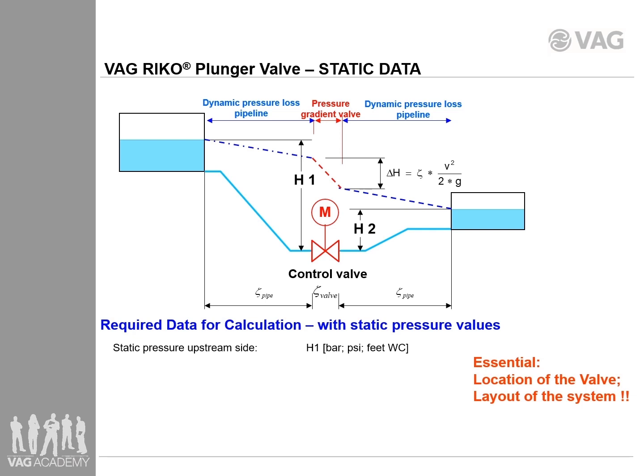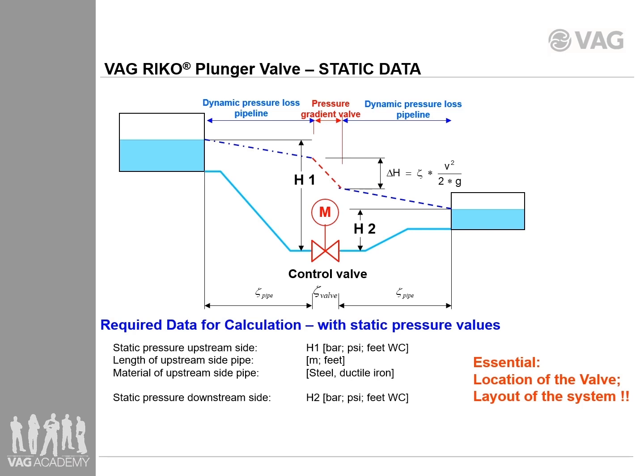You need the pipe size and the zeta value for the pipe to calculate the head loss. If the zeta value is not known, you will need the pipe length and the pipe material to calculate that through our head loss calculation program. For the downstream side, you will need the same information: the downstream pressure H2, the pipe size and the zeta value. And if you don't have the zeta value, you need the pipe length and the pipe material of the downstream pipeline.